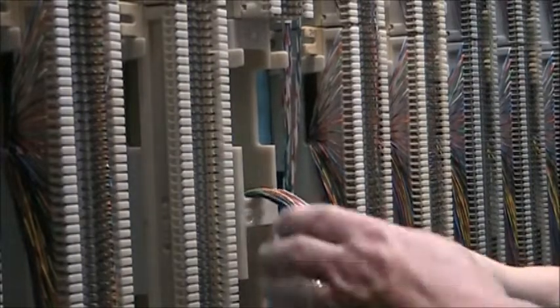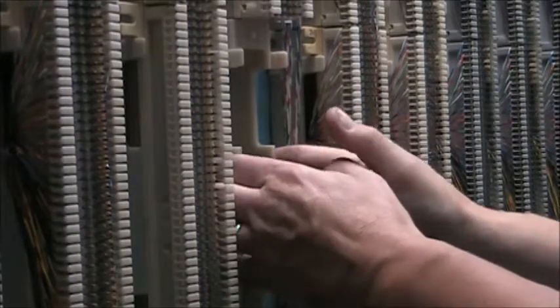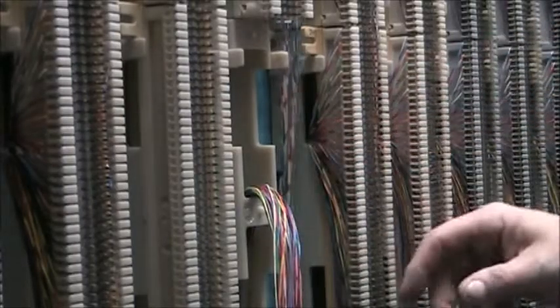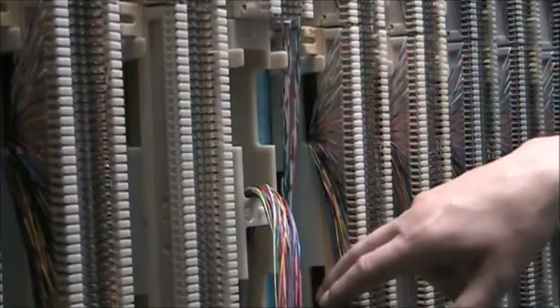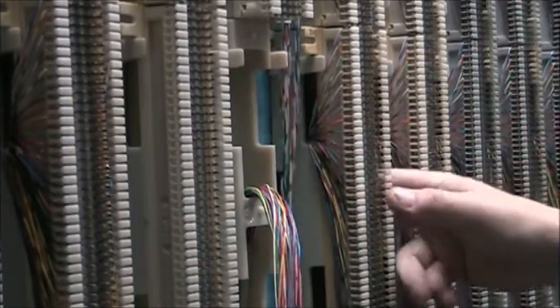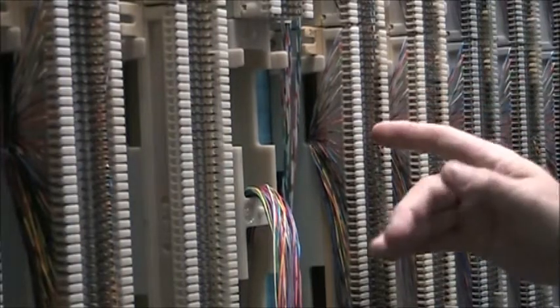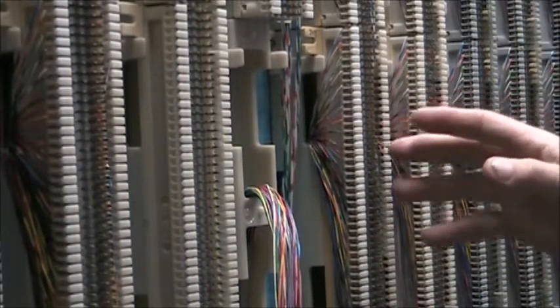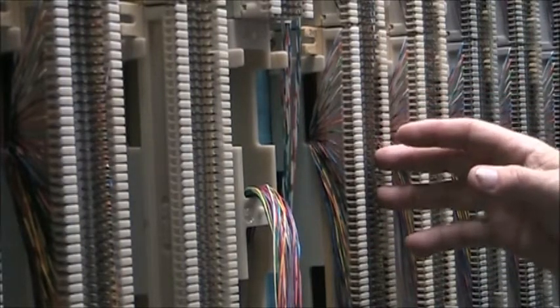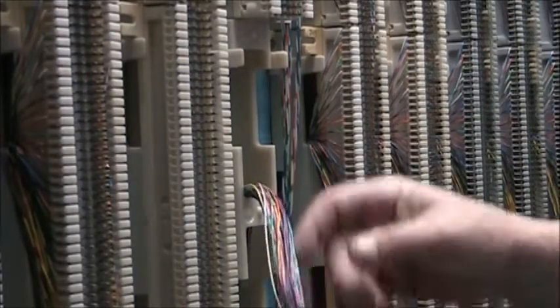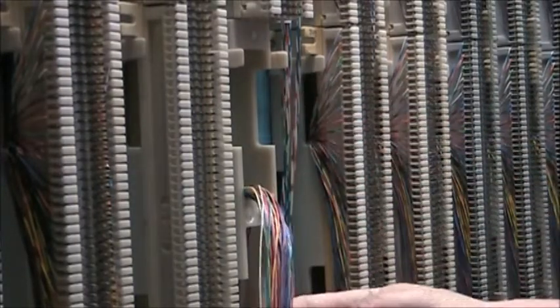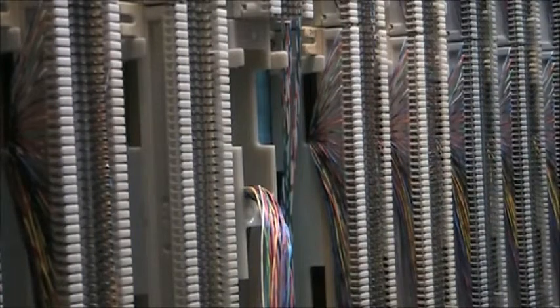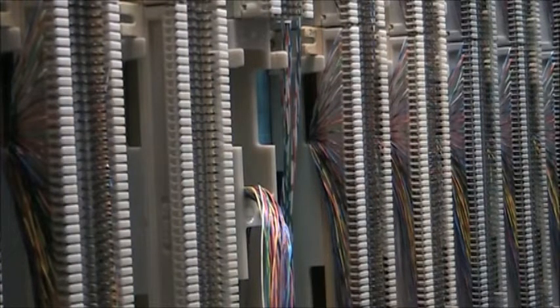You never, ever come out of the middle in the back. If you do run a cable from here out and on the other side, you cannot remove the 66 block. Having the cable coming out of the top or the bottom of the bracket on the front side, you can unsnap the block off of it and remove it.